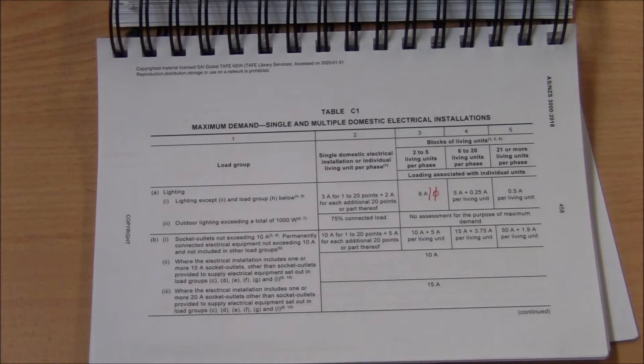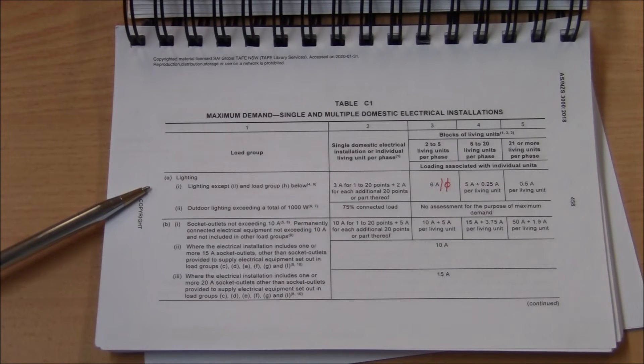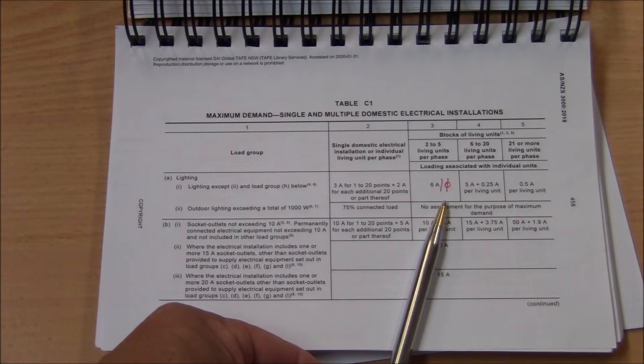First task is to identify the appropriate load group. We have 18 lighting points on the equipment list and we also have six meters of track lighting. Lights are in load group A. The quantities: 18 lighting points as well as six meters of track lighting per living unit. Column 3 indicates that lighting will contribute 6 amps per phase.